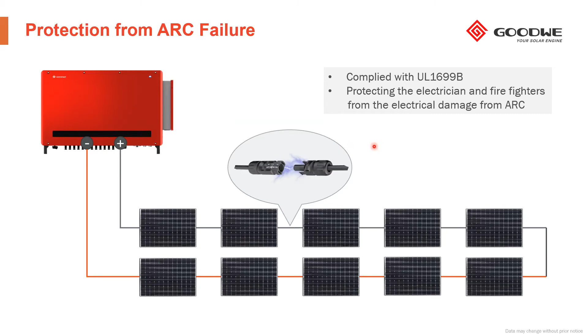Basically, this protection works so that if someone opens the DC circuit under operation, intentionally or not, there will be an arc, and the inverter will detect this arc and immediately stop that MPP tracker to protect not only that person but also the installation. This is relevant for C&I projects, especially wooden-made facilities, where this kind of protection is required by the tender or the owner.